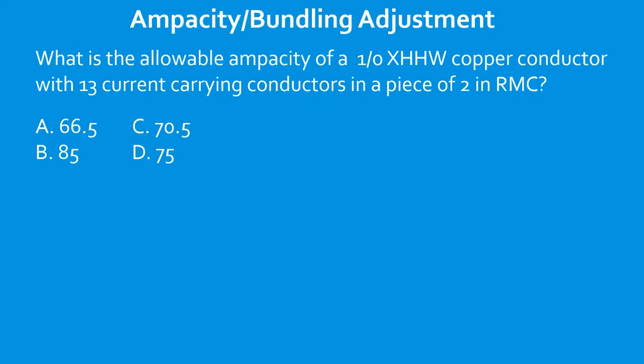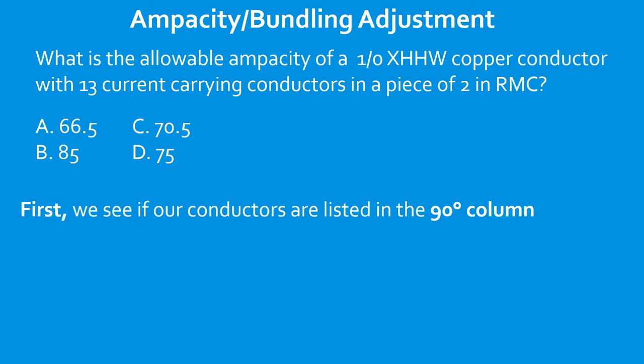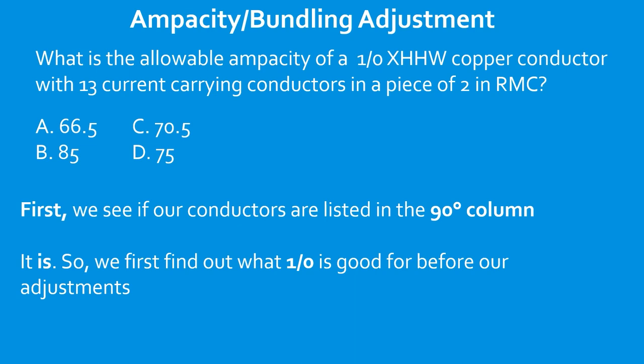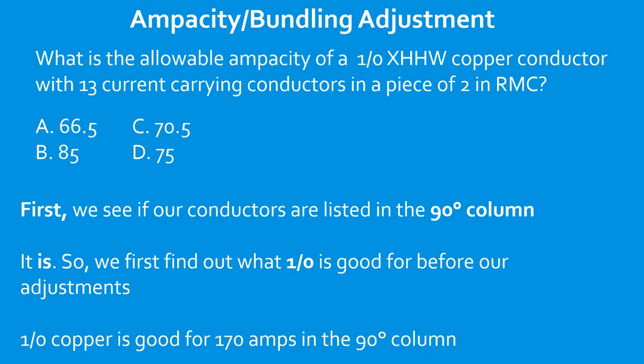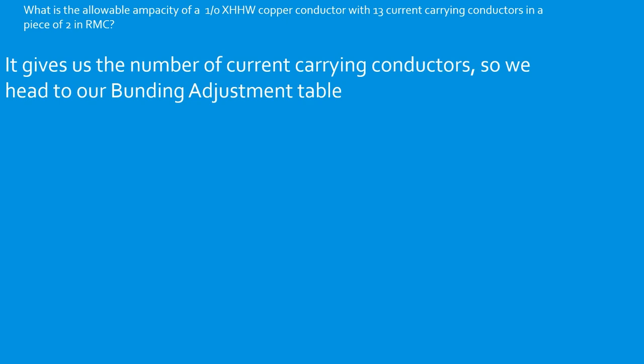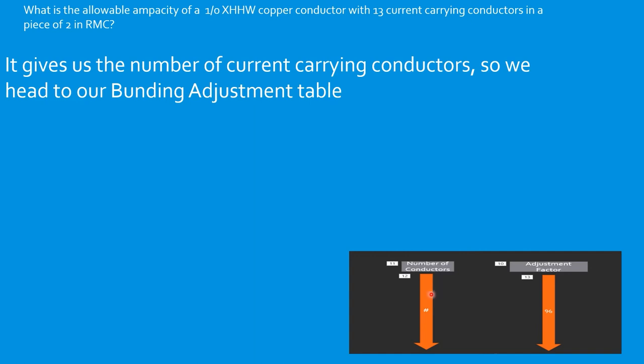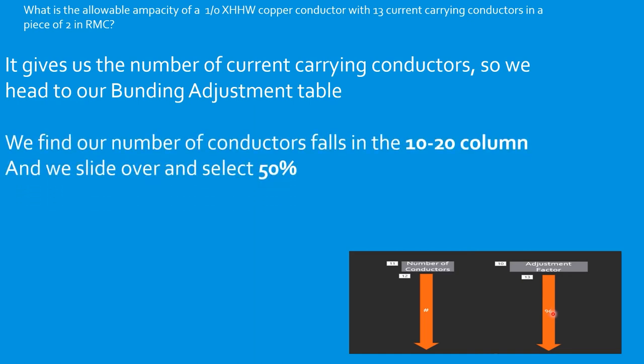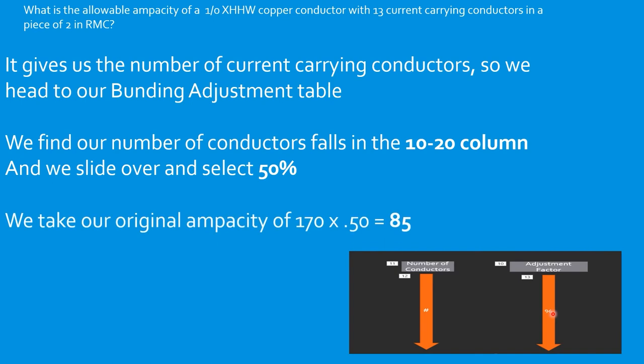Question: What is the allowable ampacity of a 1/0 XHHW copper conductor with 13 current-carrying conductors in a piece of 2-inch RMC? Confirm XHHW is in the 90°C column. A 1/0 copper is good for 170 amps in the 90°C column. Thirteen conductors — go to the bundling adjustment table and find the adjustment factor: it is 50%, or 0.50. So: 170 × 0.50 = 85 amps. Select B.